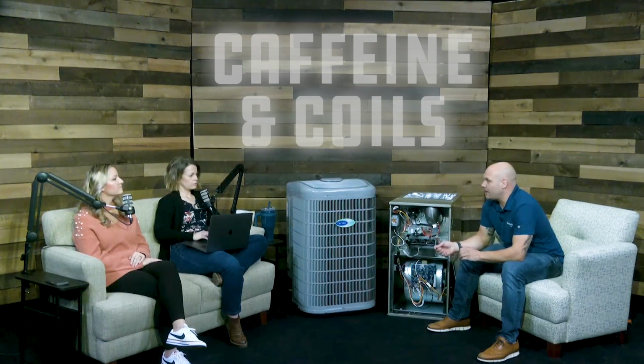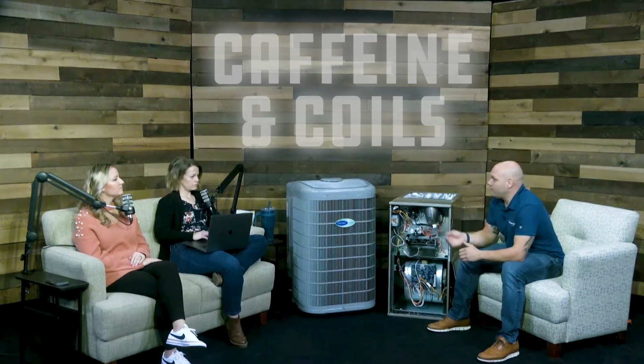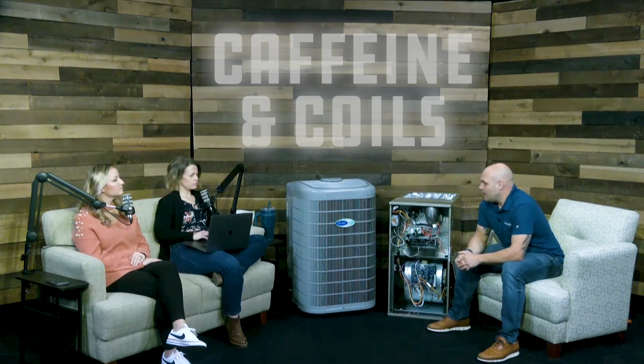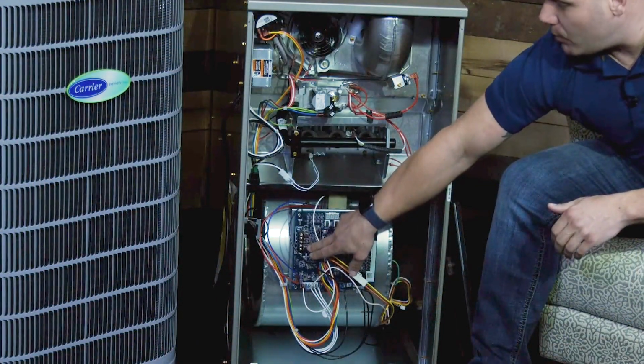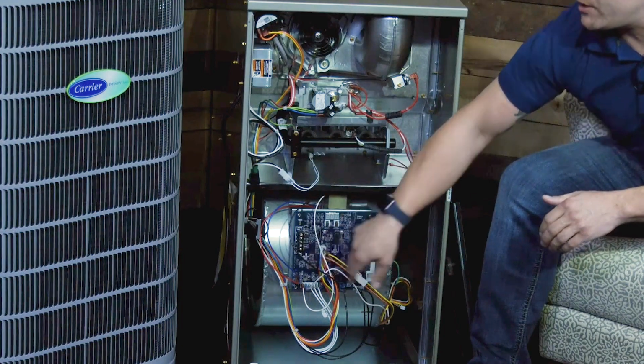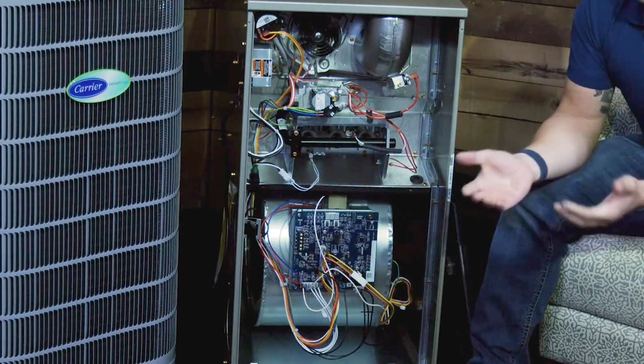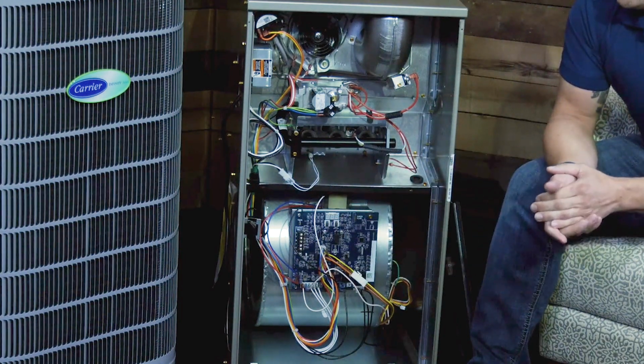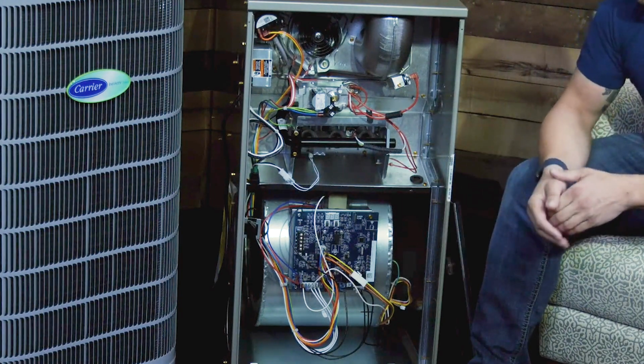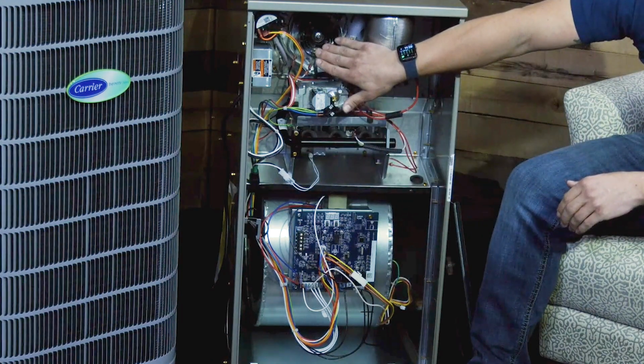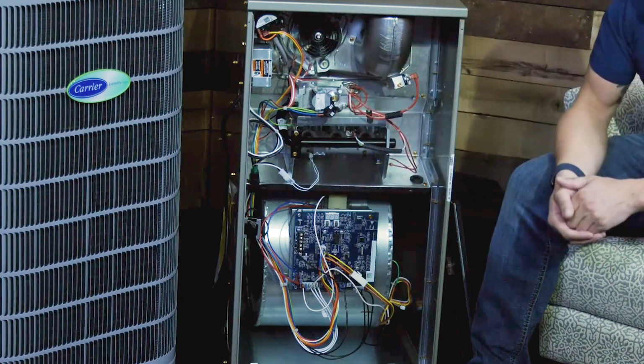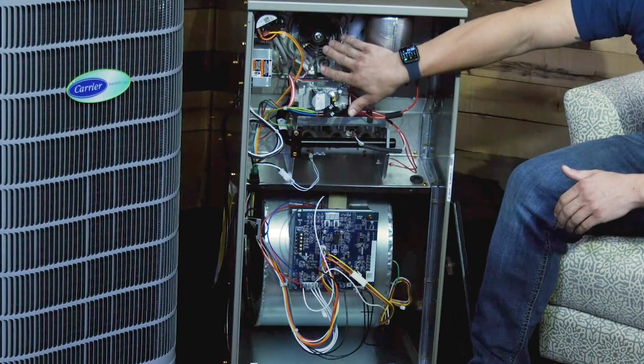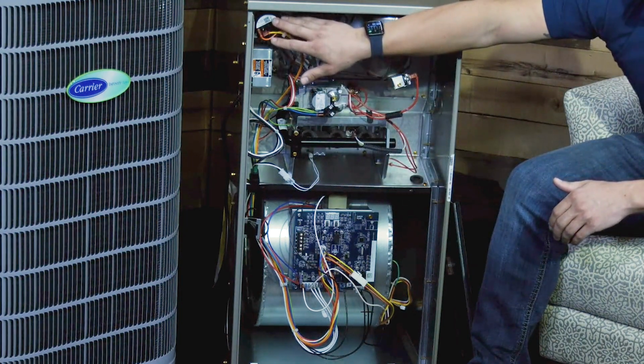So you've got your thermostat in heat mode. Your asking temperature is above the current temperature in the house. And then you should get 24 volts across C and white. These are your terminals at your furnace board. After you verify 24 volts to your furnace, the first thing that'll happen is your draft inducer motor will turn on. After your draft inducer motor turns on, it'll activate what's called a pressure switch. So that's step 2, your pressure switch.